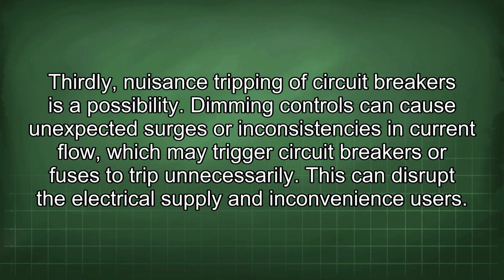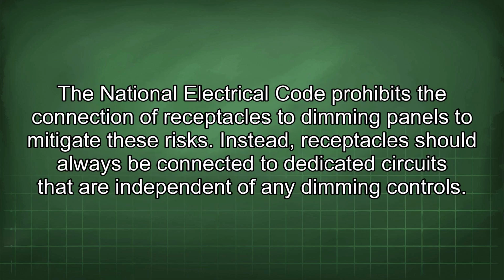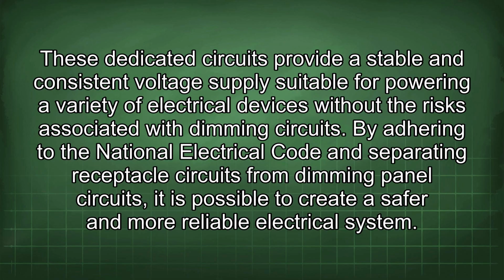Thirdly, nuisance tripping of circuit breakers is a possibility. Dimming controls can cause unexpected surges or inconsistencies in current flow, which may trigger circuit breakers or fuses to trip unnecessarily. This can disrupt the electrical supply and inconvenience users. The National Electrical Code prohibits the connection of receptacles to dimming panels to mitigate these risks. Instead, receptacles should always be connected to dedicated circuits that are independent of any dimming controls. These dedicated circuits provide a stable and consistent voltage supply suitable for powering a variety of electrical devices without the risks associated with dimming circuits.